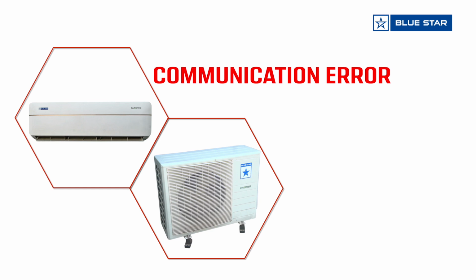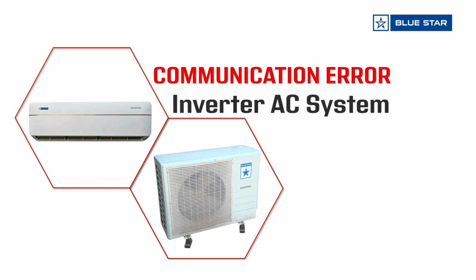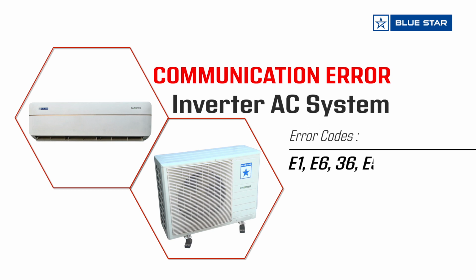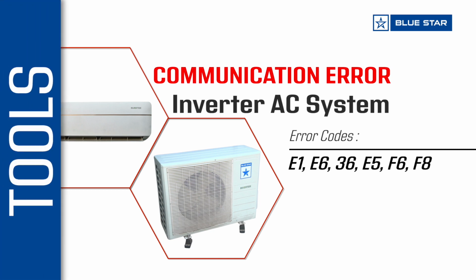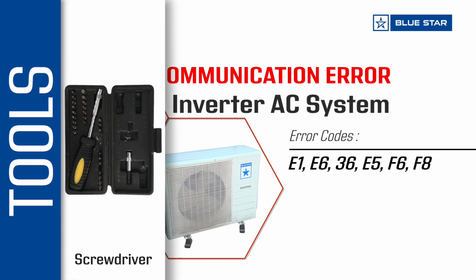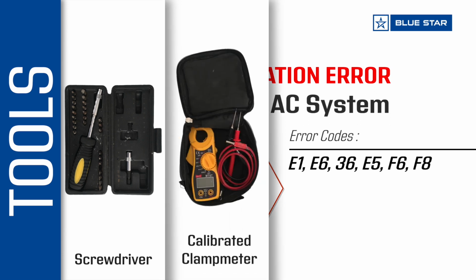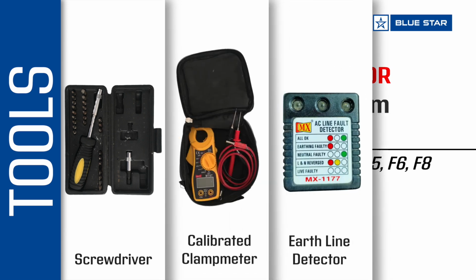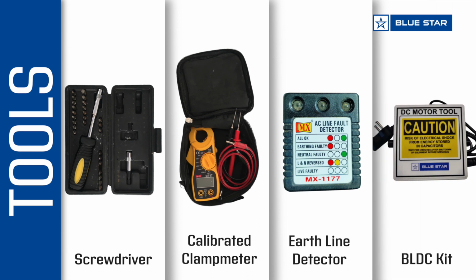Note that this error occurs only in an inverter AC system and not in a fixed-speed compressor AC. When this error occurs, depending on the system model, the indoor unit shows E1, E6, 36, E5, F6, or F8 error code on the IDU display. Let's have a look at the different tools required to resolve the error. You need a screwdriver kit, calibrated clamp meter, earth line detector, and BLDC kit.